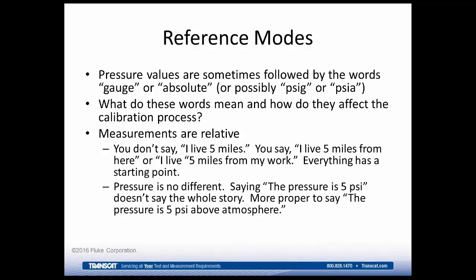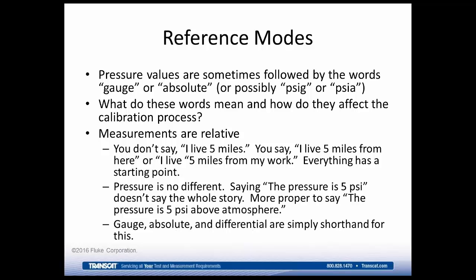Saying that the pressure is 5 psi and only saying 5 psi doesn't say the whole story. It doesn't give you all the information that you need. The long way of saying it, the more proper way, would be to say something like, the pressure is 5 psi above atmosphere. But that's kind of a long-winded statement and will not be very effective when you've got a lot of different pressure values that you're looking at. So the terms gauge, absolute, and differential are simply shorthand for this.